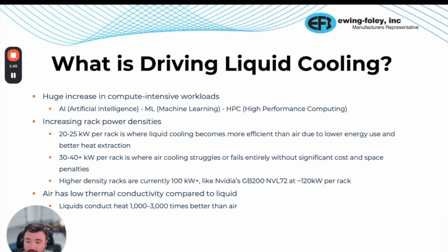Why? At 30 to 40 kW per rack, air cooling systems really start to struggle, or they just fail outright. NVIDIA's GB200, the NVL72, for example, is pushing almost 120 kW per rack. That's a lot of heat. At these densities, air just can't keep up.